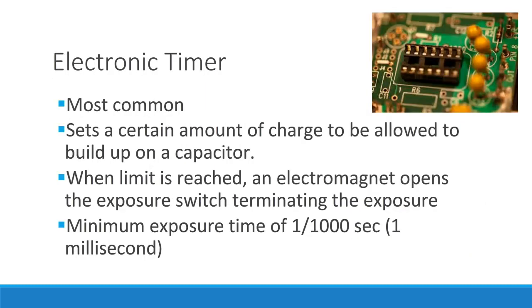The electronic timer is the most common timer utilized today. It sets a certain amount of charge to be allowed to be built up in a capacitor — any device that stores an electrical charge. When this electric charge limit is reached, the capacitor discharges its current, which causes an electromagnet to open the exposure switch, terminating the exposure. These timers are very accurate and can produce exposure times of 1 ms.